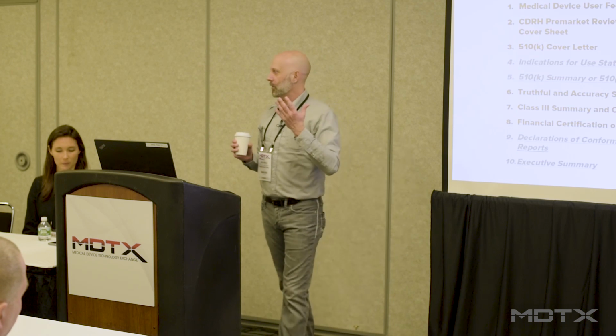Now, I know none of you will ever make this mistake. But I've looked at a lot of 510Ks. Somebody will send the submission to me, and they'll ask for my comment, and they have a different statement in each section. Like its words are different. How can that be? And is that a big deal? Yeah, it's a big deal, because that statement is the whole basis for your 510K argument. So it's going to be in multiple places. Do yourself a favor. Make sure it is verbatim, word for word, exactly the same everywhere it's referenced. I know you think I'm beating a dead horse here, but that's one of the biggest reasons why a 510K gets rejected.